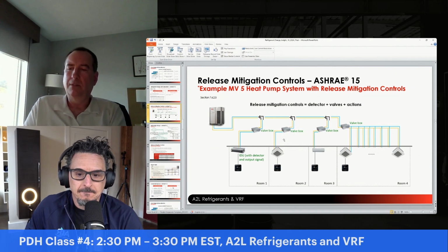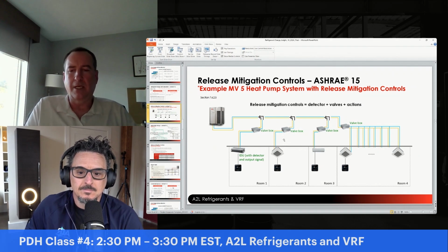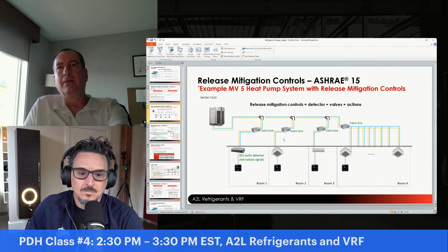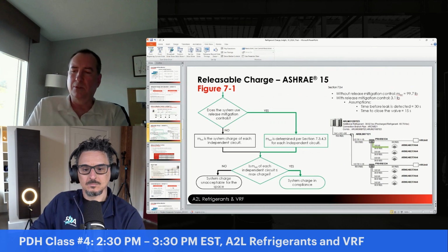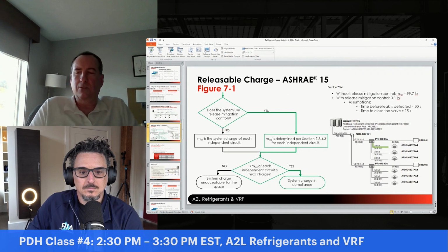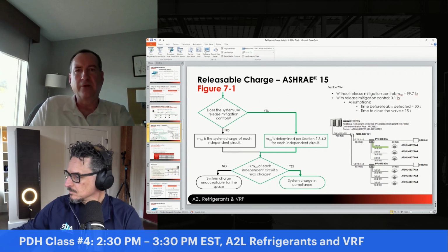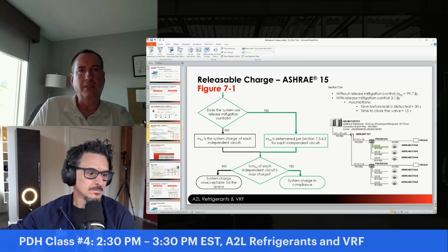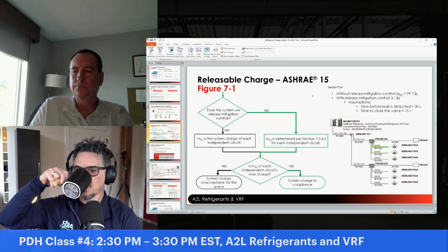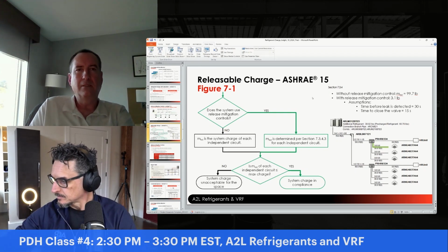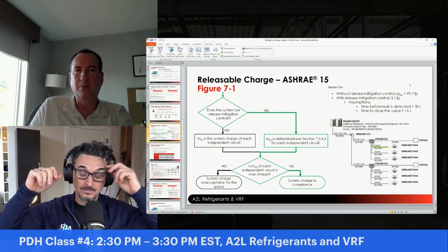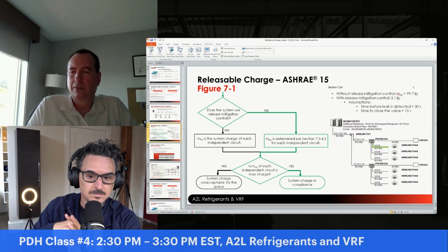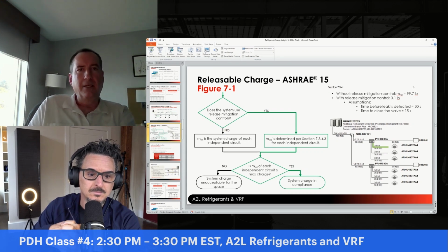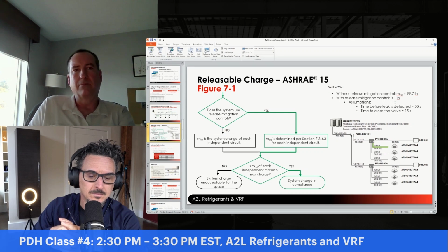That's good. Yeah. So additionally, we've got controls that can trigger other mitigation actions like air circulation, ventilation, opening zone dampers in the ductwork, if you have any things like that. And then that moves us to this concept of releasable charge. So with release mitigation controls, ASHRAE introduced this concept, and the variable for it is MREL, as you see here. Basically, M release is the variable. So in this example, you can see that without these mitigation controls, this variable is 100 pounds. So that's the entire charge of the whole system. And then with these mitigation controls, that charge is reduced down to about 3 pounds.